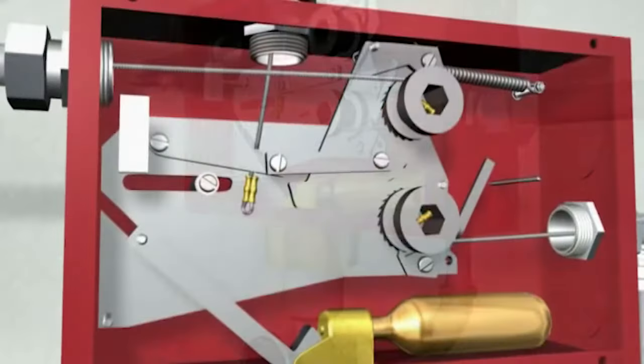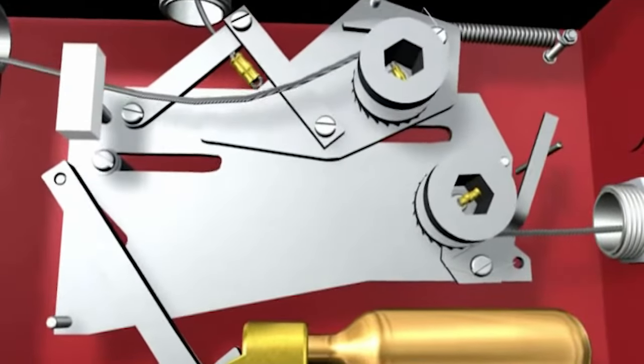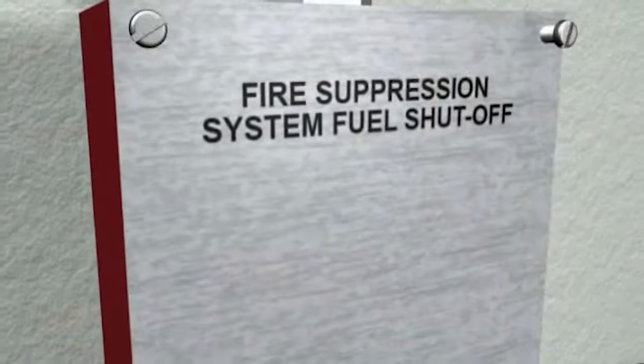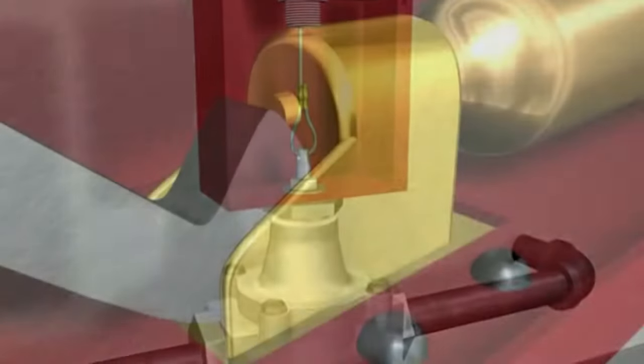The Kitchen Knight 2 system can also be actuated by a manual pull station. This action initiates electric power shutdown and the mechanical control head to release tension to a separate wire that triggers the gas valve to shut off.